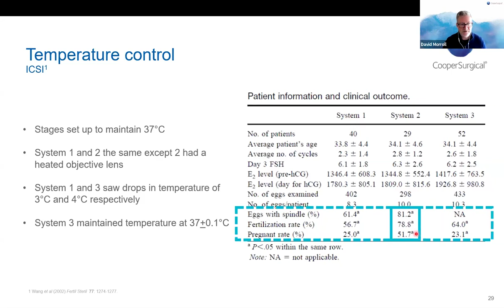Now, of course, when you do ICSI on an inverted microscope, the objective of the inverted microscope is very close to the underside of the dish, and therefore it acts as a heat sump and causes cooling. And this is demonstrated here. This is a thermal image of a heated stage on an ICSI microscope with an aperture, and as you expect, you get cooling. Now, if you see the same thing with a heated glass stage, you still get this cool spot in the middle, and again, that's because of the objective lens acting like a heat sump and causing cooling right over the area where you'll be working. And that's why we use the thermosafe system, this system of blowing warmed air onto the underside of the dish to solve that problem. It warms the objective and it keeps the underside of the dish warm.